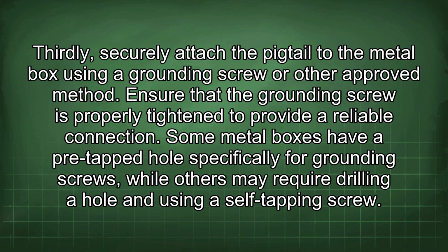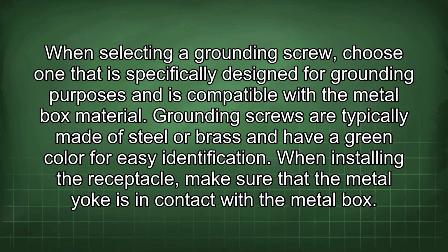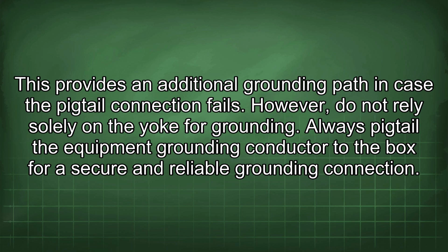Some metal boxes have a pre-tap hole specifically for grounding screws, while others may require drilling a hole and using a self-tapping screw. When selecting a grounding screw, choose one that is specifically designed for grounding purposes and is compatible with the metal box material. Grounding screws are typically made of steel or brass and have a green color for easy identification. When installing the receptacle, make sure that the metal yoke is in contact with the metal box. This provides an additional grounding path in case the pigtail connection fails. However, do not rely solely on the yoke for grounding. Always pigtail the equipment grounding conductor to the box for a secure and reliable grounding connection.